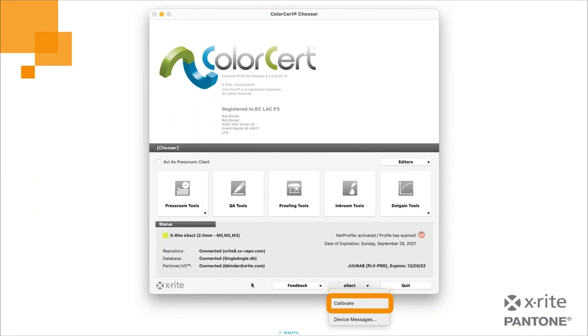The next thing we can do is calibrate the instrument. Clicking this button will, with the Exact, be very quick because, as you know, the Exact is able to calibrate itself. So if I click this button, the device just begins its calibration routine. With the CI64, as you know, that device is not able to calibrate itself, as the Exact is. And at least for myself, I find it easier to calibrate that device through the software than through the instrument display. This just takes me right to the calibrate section within the CI64, and I can immediately begin calibrating.